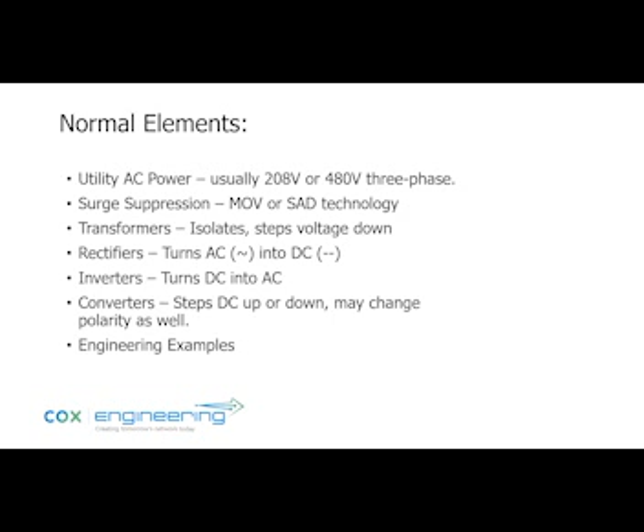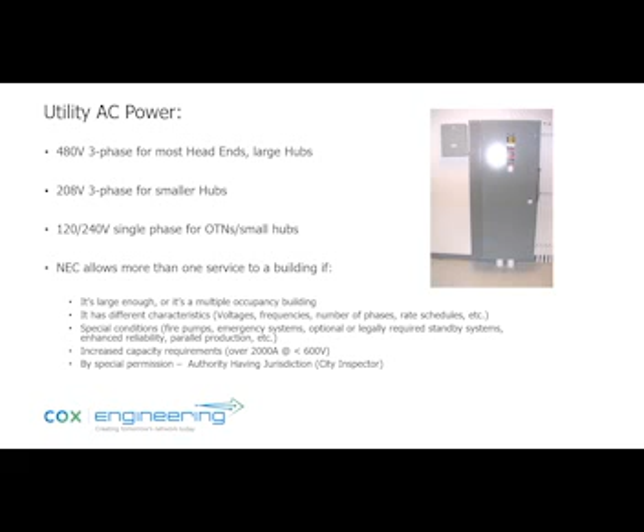So your utility AC power is coming in. There's a main knife switch behind that panel. 480 or 208 3-phase, depending on the size of the hub or head end. 120 or 240 for small hubs. And the NEC allows for more than one service. That's the National Electrical Code, to a building if it's a certain size or there's increased capacity requirements. But the AHJ, the authority having jurisdiction, is always the last word on any of those types of things.